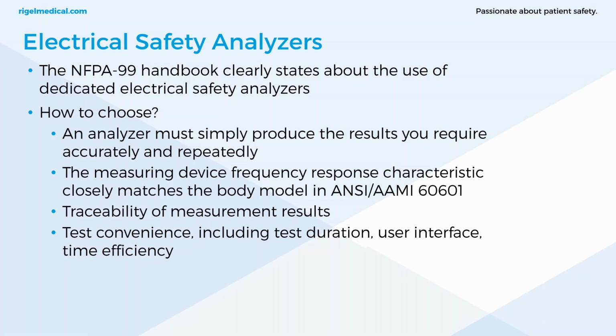So electrical safety analyzers. The NFPA 99 handbook clearly states about the use of dedicated electrical safety analyzers. So how do you choose? Well, an analyzer must simply produce the results you require accurately and repeatedly. They must have a body model similar to IEC 60601 and traceability of measurement results.